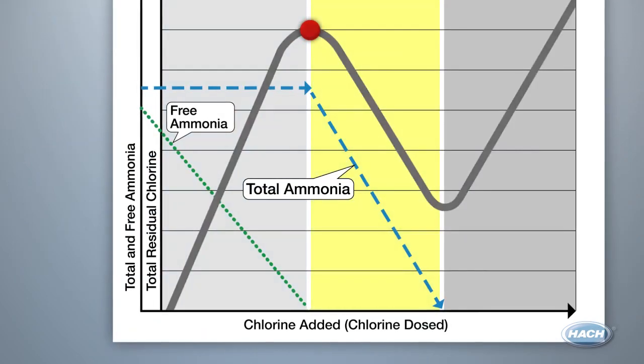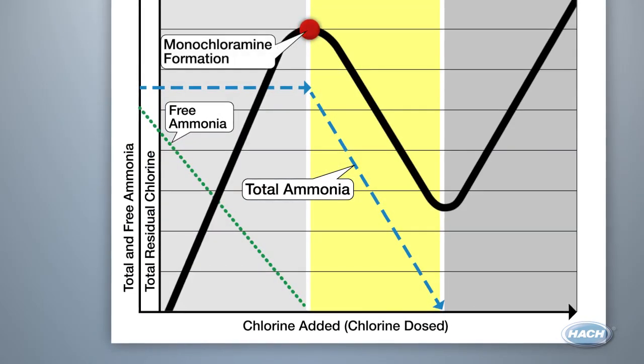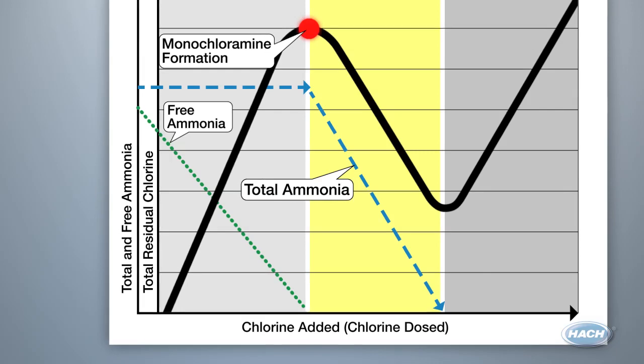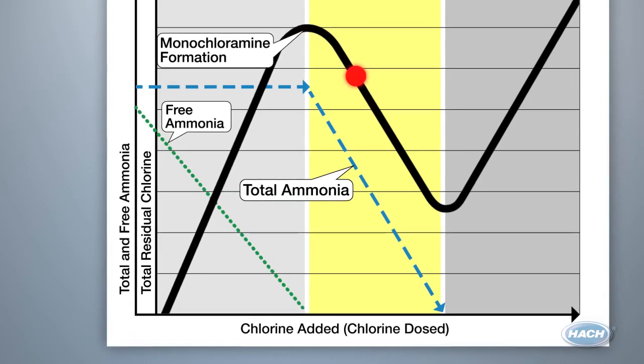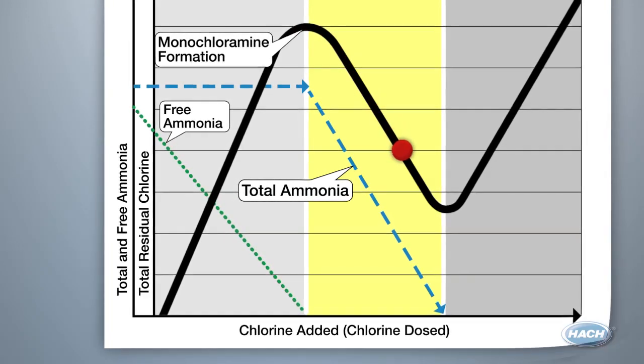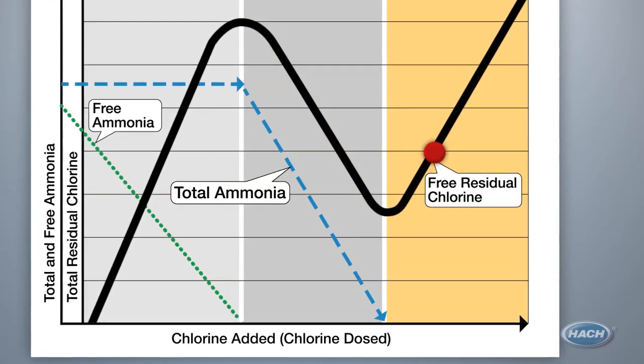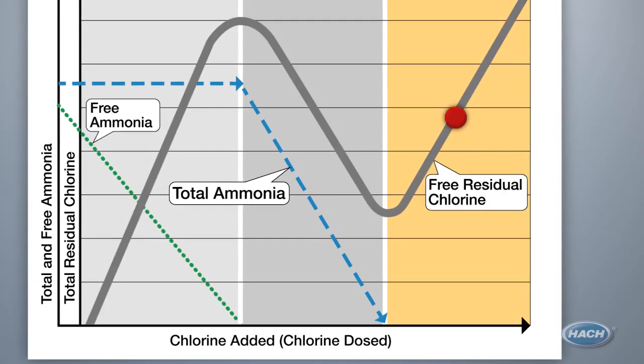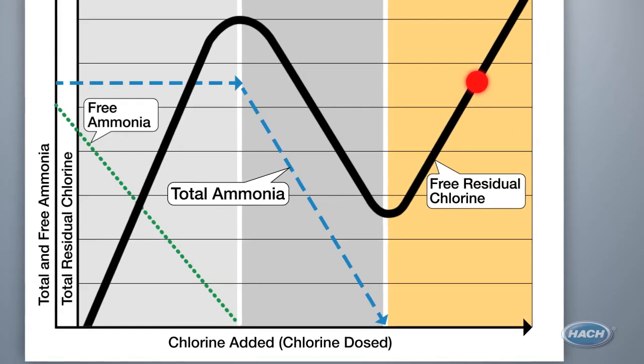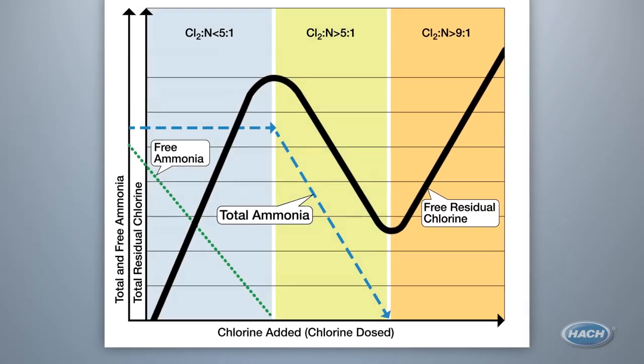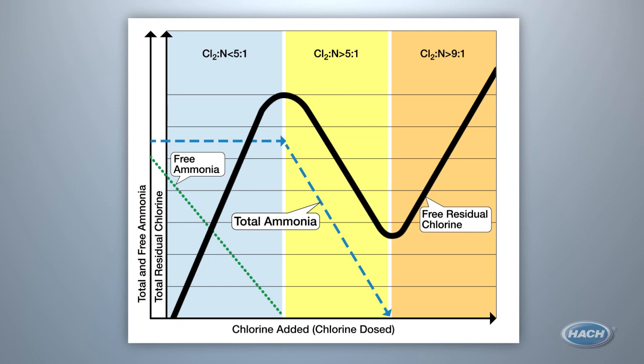In zone two, you will see total chlorine, monochloramine, total ammonia, but no free ammonia. In zone three, you will see no ammonia and only chlorine, and your free and total chlorine values should be very similar or match. If you know the key parameters to look for in each section, it is easy to determine where you are on the chloramination curve.